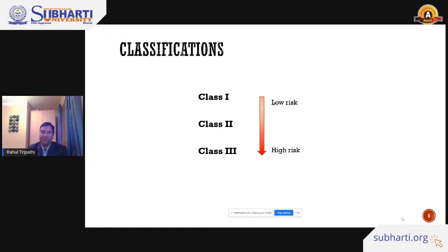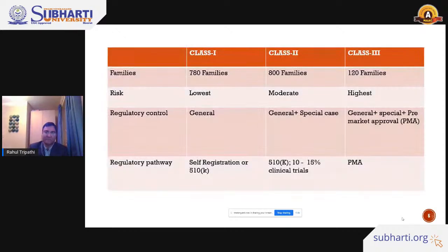So based on the risk associated with the medical devices, they have been classified according to the classification system in the FDA. I'm going to address why the classification system is important, how it works, and what the examples of class 1, class 2, and class 3 medical devices are, based on risk from low to high. So just remember, class 1 is the low risk class of medical device, and class 3 is the high risk class. That makes it a lot easier to understand the classification systems.